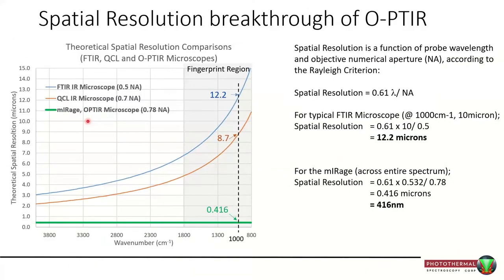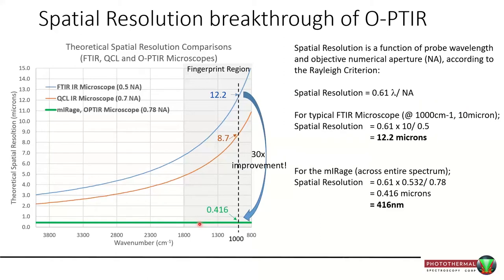Spatial resolution is another key differentiator of OPTIR. Using the Rayleigh criterion, resolution is highly wavelength dependent. With a regular numerical aperture on an FTIR objective, spatial resolution can be up in the low teens of microns in the fingerprint region, improving to maybe three microns in the high wavenumber range. With OPTIR, because the probe wavelength is fixed, so too is the spatial resolution. With a short-wavelength laser and high numerical aperture objective, the theoretical resolution is just over 400 nanometers — fixed along the entire wavelength range, representing roughly a 30x improvement over regular IR in the fingerprint region.